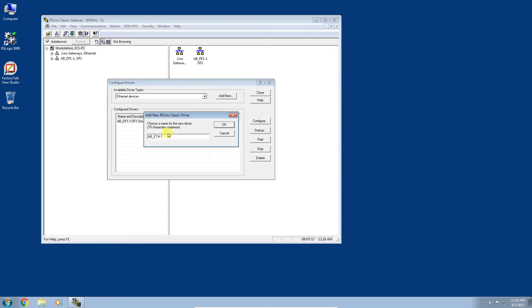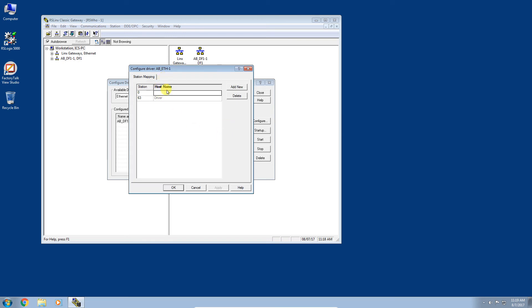Click Add New. You can give this driver a unique name — I recommend this if you're in a facility with many PLCs and work cells, so you can modularize controllers by area or description. For now, we'll keep the default and click OK. With the Ethernet Devices driver, we need to statically type in the IP address of the controller or controllers we want to connect to. My controller communicates over the Ethernet bridge module at 192.168.1.10, so I'll click Add New, click Apply, and click OK.